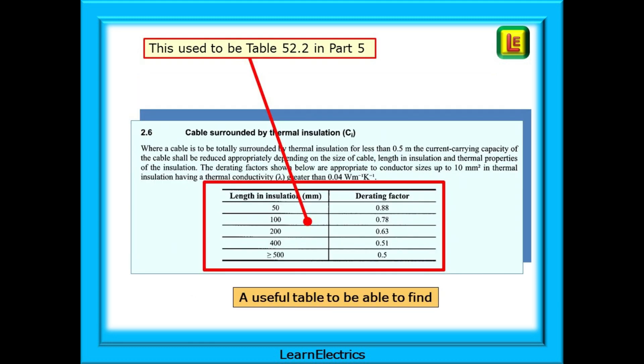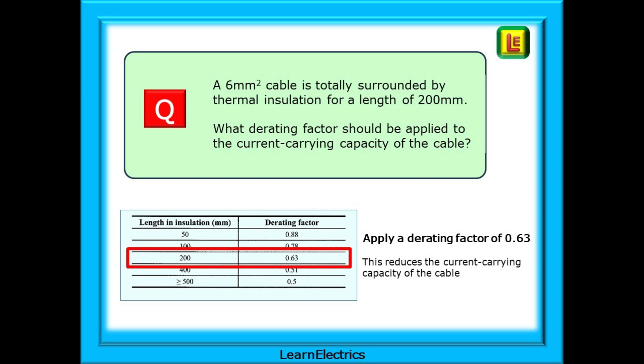This is the table that used to be in part 5 of the book. Now it is item 2.6 in appendix 4 and no longer listed as a named table. It is a very useful item to be able to find as it is a popular choice with the exam question setters. So to answer our question, what derating factor should we apply to our 6 millimetre cable? Item 2.6 gives the answer. For a cable totally surrounded by thermal insulation for 200 millimetres of its length, we should apply a derating factor of 0.63. This effectively reduces the current carrying capacity of the cable.